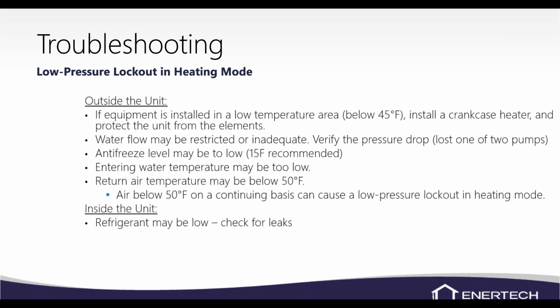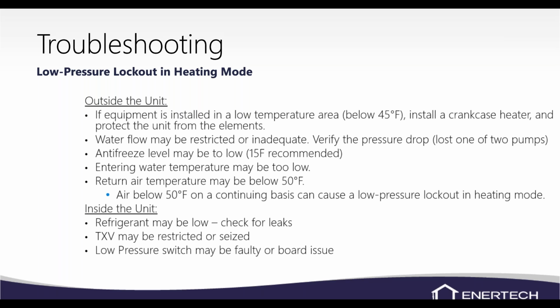Inside the unit, obviously low pressure refrigerant. If you are low on refrigerant, you've got a leak somewhere. So make sure you're checking for refrigerant leaks. TXV could be stuck closed. Basically, we're going to pump down when that TXV gets restricted like that. So it could be a TXV issue. Again, low pressure switch or board as well. You know, make sure we're always checking those components as well.